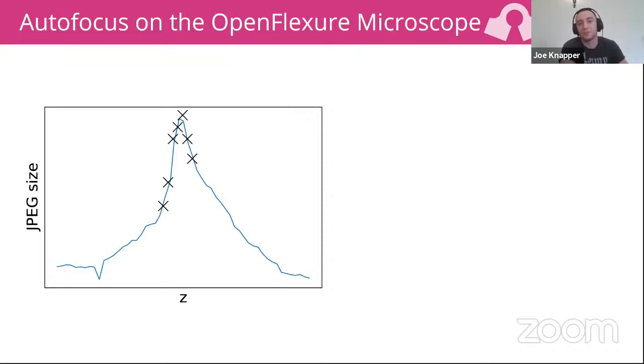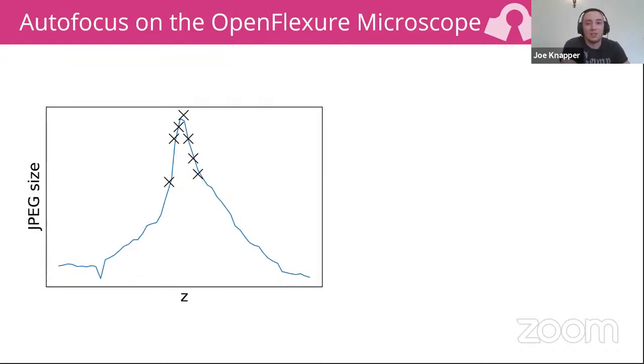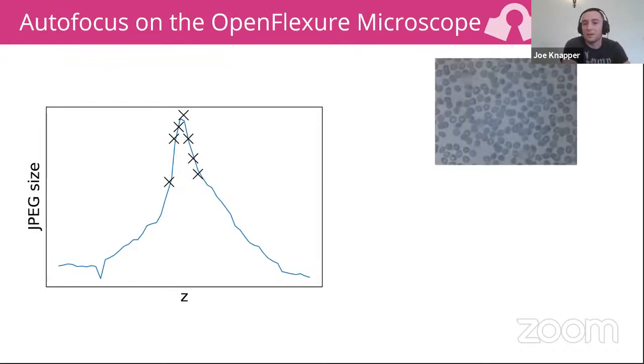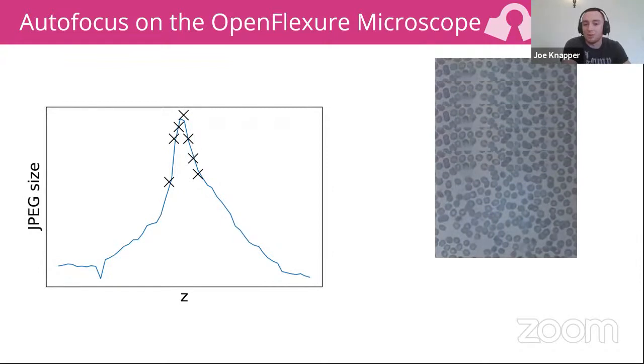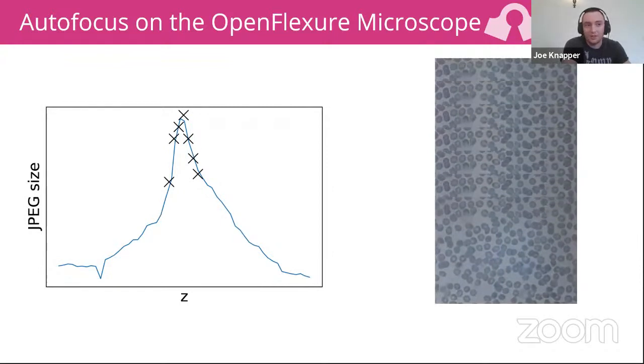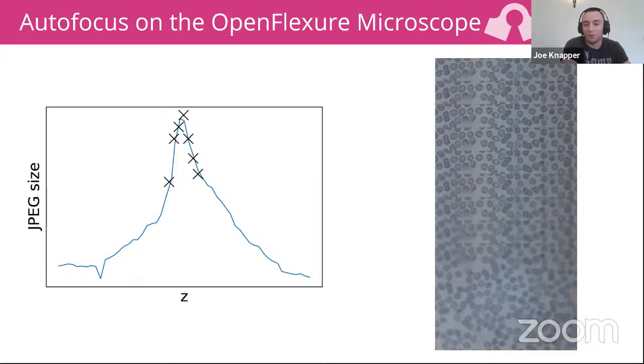For example, here you can see that the first image in the stack is slightly out of focus, going through 9 more images. The center image was more focused than the others, and then the system begins to defocus again. This is what we'd expect to see around the focal plane. If we don't see that, we know there's been a problem with the sample or the focusing, and we can restart or inform a technician.